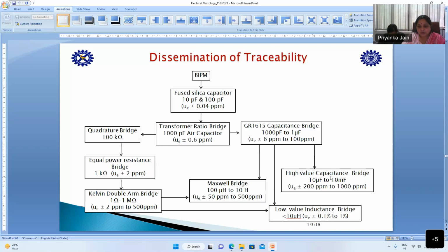And then we have a high value capacitance bridge, where we can calibrate from 10 microfarad to 10 millifarad range, and uncertainties are 200 ppm to 1000 ppm. And we have a low value inductance bridge also, which can define the inductors from 0.1 microhenry to 10 microhenry. Recently, we have established the facility for 1 microhenry and 0.1 microhenry. Earlier, we had only the 10 microhenry facility. So this is our latest development.